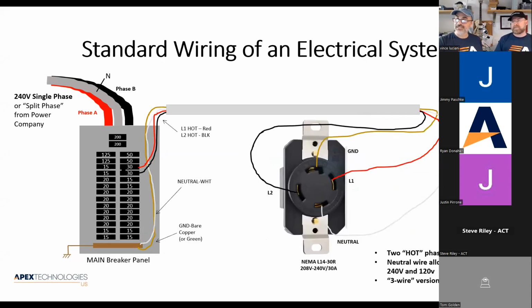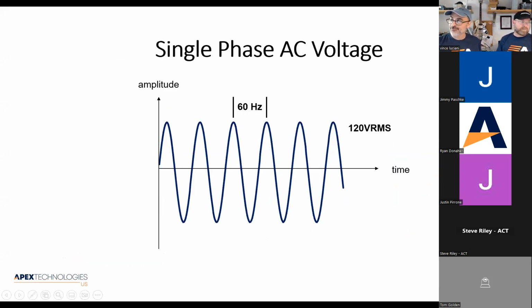So just for completeness, I showed how a higher voltage, a 240 volt outlet, is connected. I used the locking style. I think when you have a big hefty connector, we're in an industry where everybody does everything first class, so you want to use a locking connector. I just happen to use the locking connector that is 4-wire. So what's the difference between a 4-wire and a 3-wire?